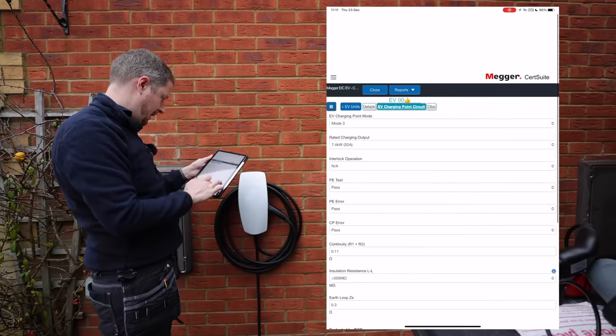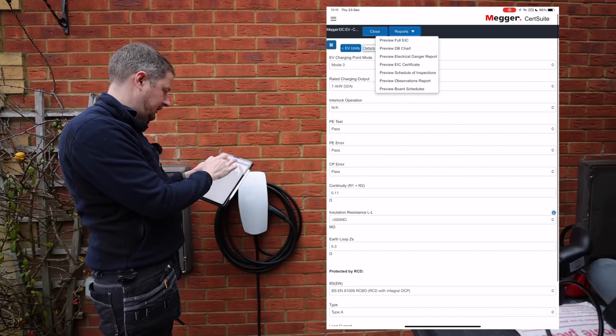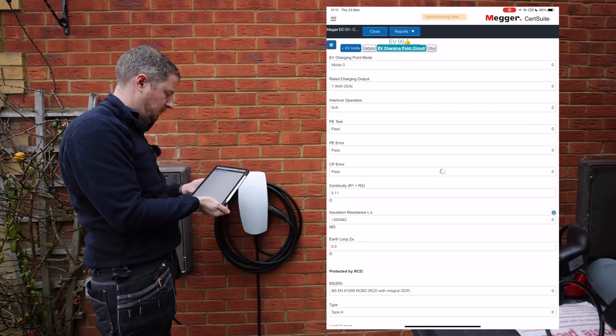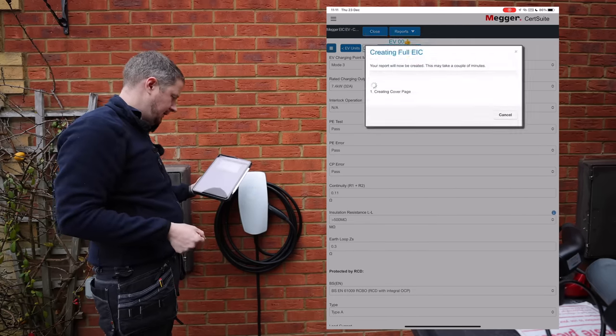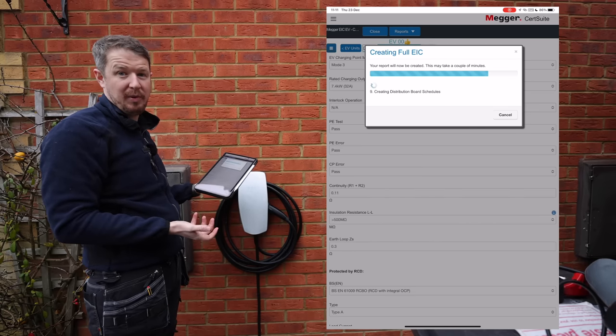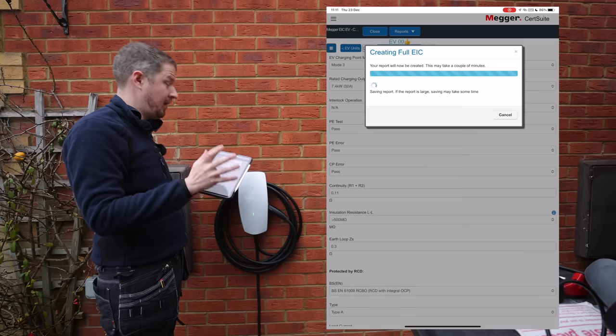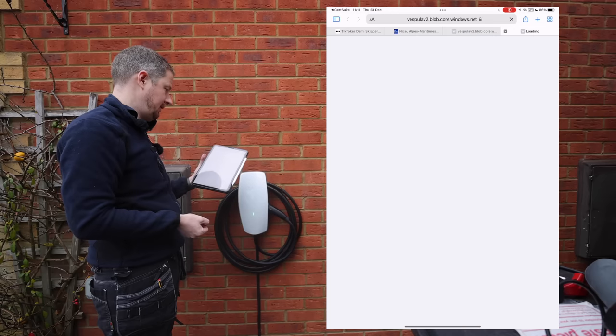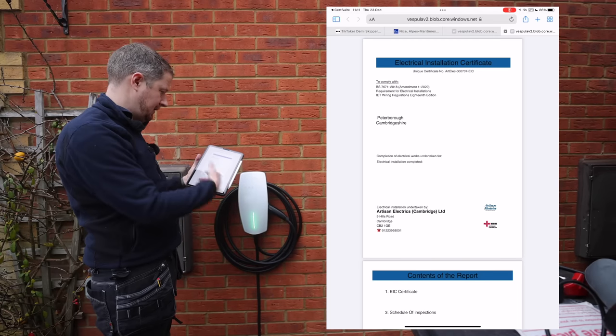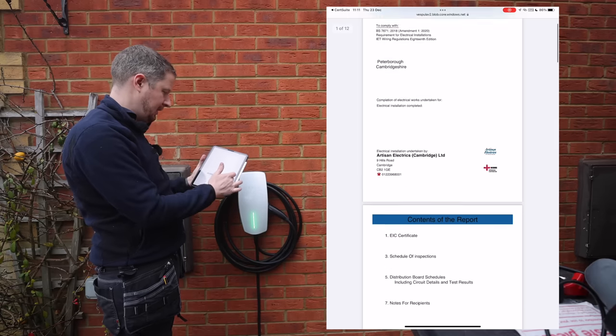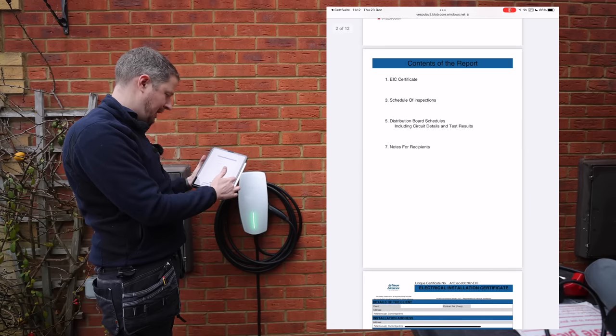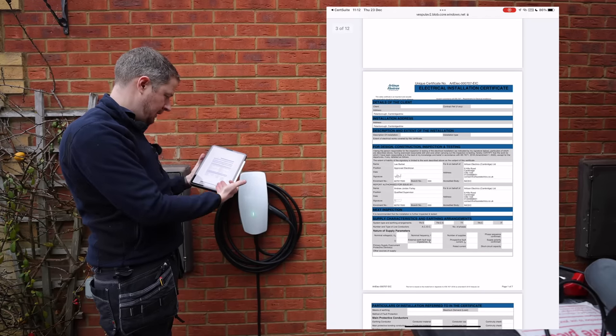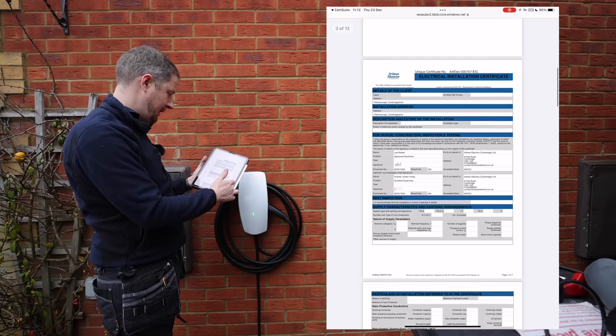So we go through now, and for our RCD test we've got 26.1 is our highest for one times, so we put that in, 26.1. And then five times was 15.8. Now I'll make sure all my details are all filled in, which they are. Click reports, click preview, add signatures, and then it'll create a PDF preview of the report that I'm going to send to the customer. And you'll see just how good-looking these things are, they really, really look nice.